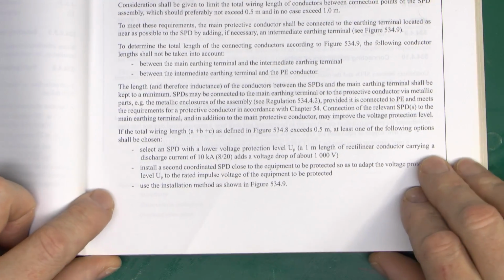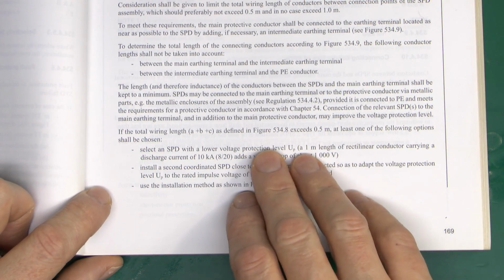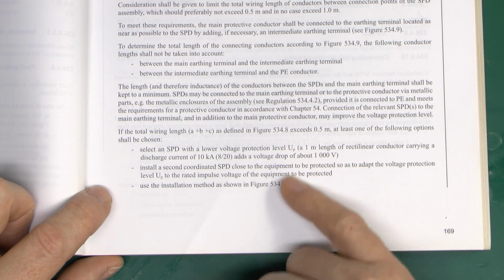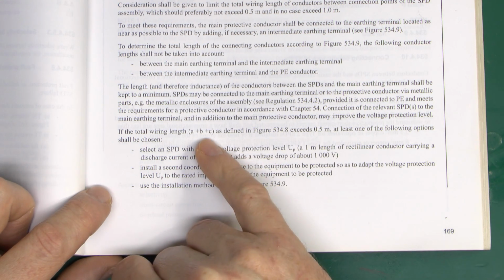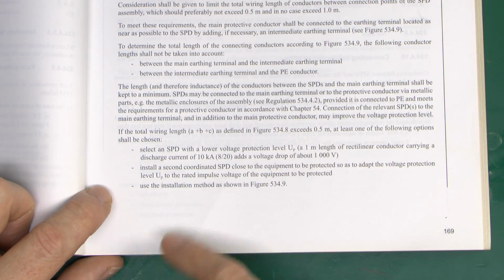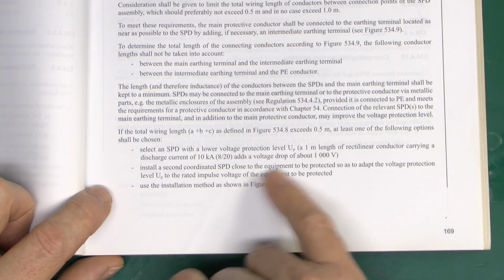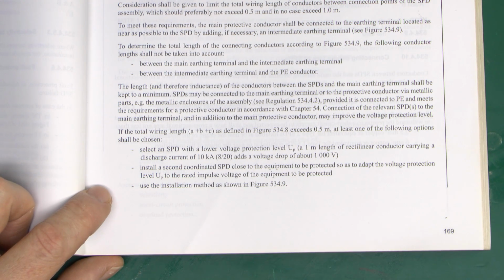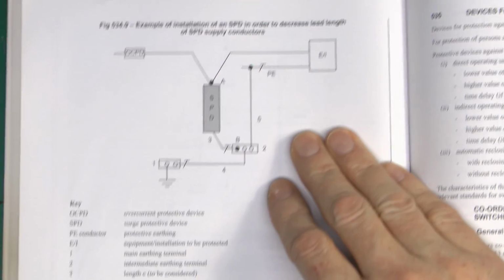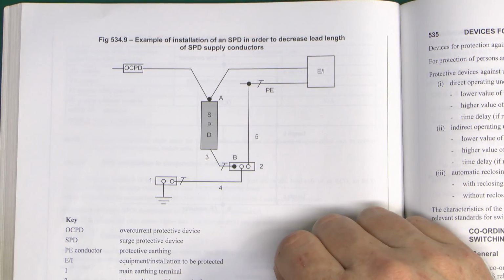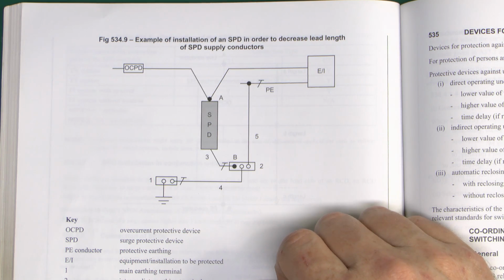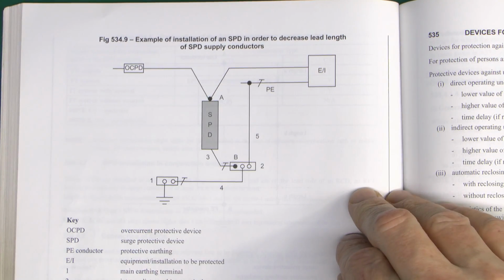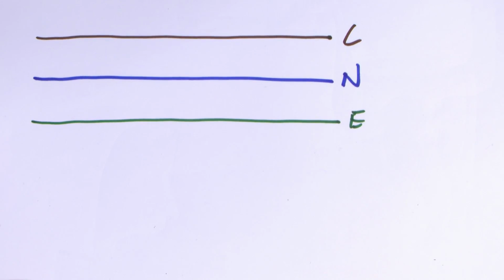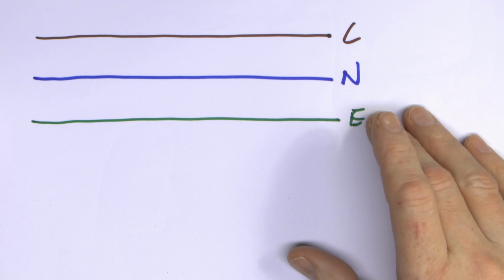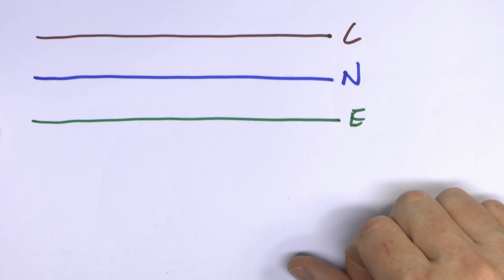And there's a bit at the bottom here which says if the total wiring length as defined there exceeds half a metre, then you've got various options here. But really the option is to make the wiring length less than half a metre, because some of these options here are certainly not optimal, and there can be other problems with having excessive lengths of wiring. Now there's a diagram here which attempts to explain what lengths of wiring we're actually measuring, but it's not particularly helpful and it's rather confusing, so we're not going to be bothering with that. Let's just move away and draw one ourselves. Now here we've got a typical set of wires, so line, neutral and earth, as you would find in the installation.